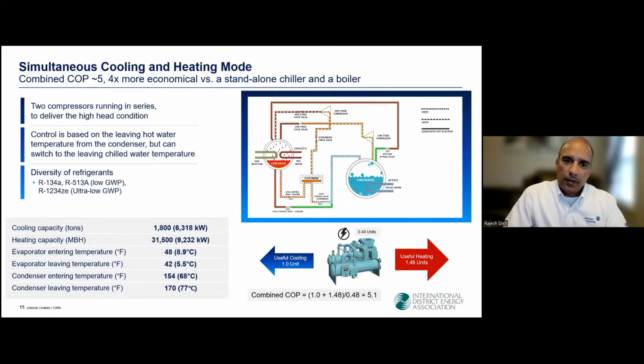For every 1 unit of heat that is removed from the evaporator, 0.48 units of input energy is required to drive the compressors. Therefore, the 1 plus 0.48 is equal to 1.48 units of heat available from the condenser. Thus, the combined COP becomes 5, which is almost 4 times higher than a conventional standalone chiller and a standalone boiler system. Basically, one equipment does it all, smartly moving the BTUs around rather than creating them.